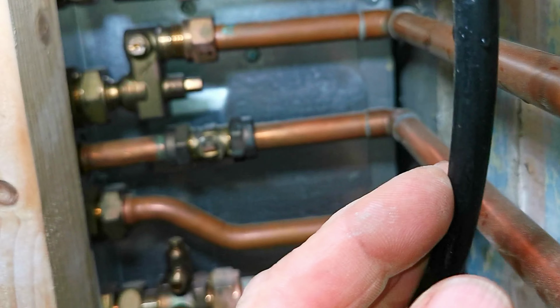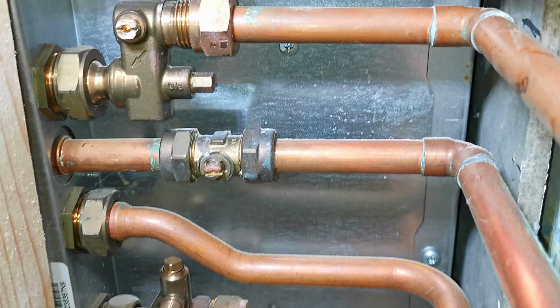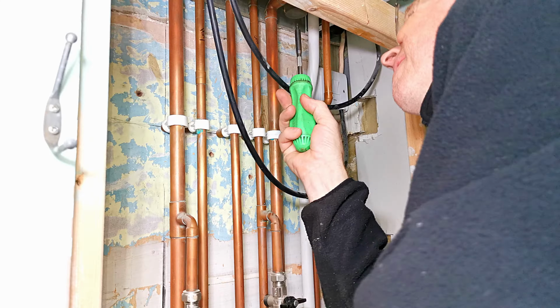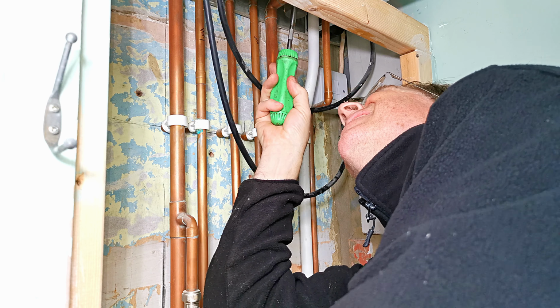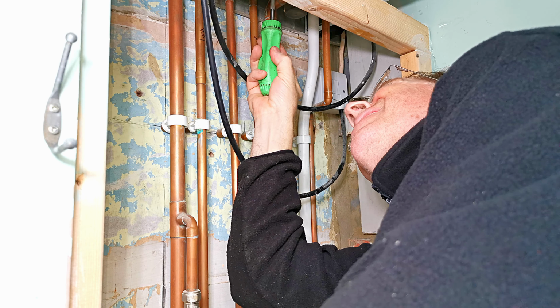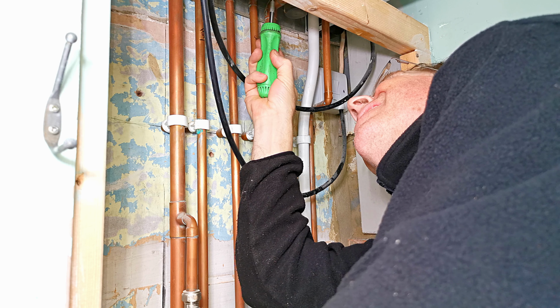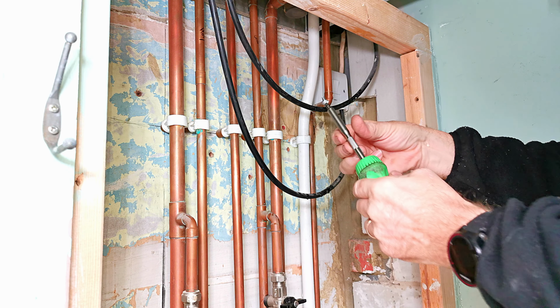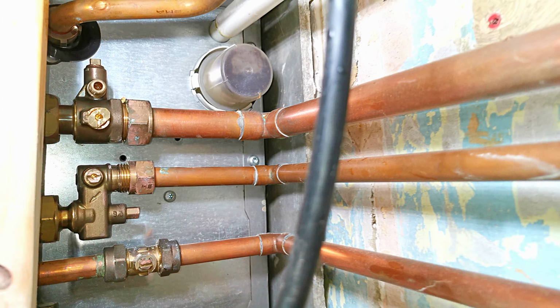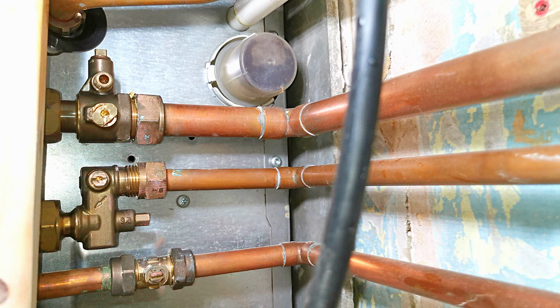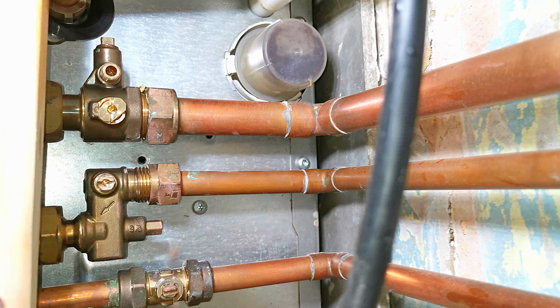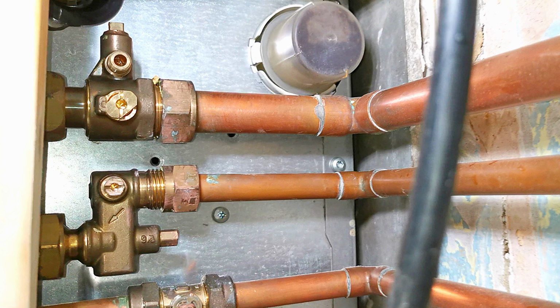Now because I'm not going to remove the diverter valve, I need to undo 2 additional screws on the bottom of the boiler. One of them's quite easy to get to, the other one is a little bit tricky because it's on a slight angle because it's hidden by one of the pipes. So that's one of the screws there. You can now see I've removed both of those screws, and they hold the bracket which hold the pump housing.